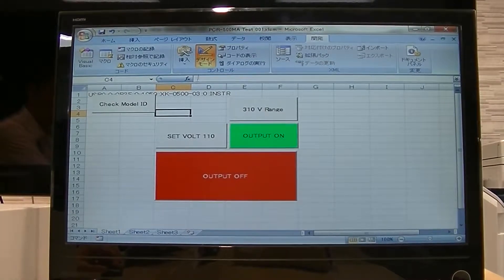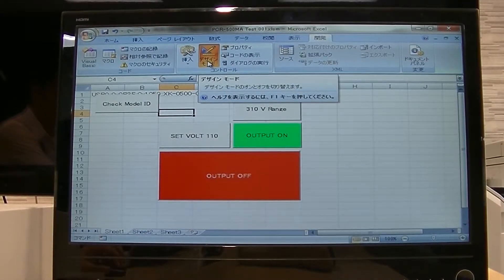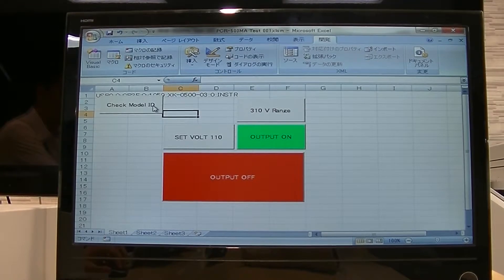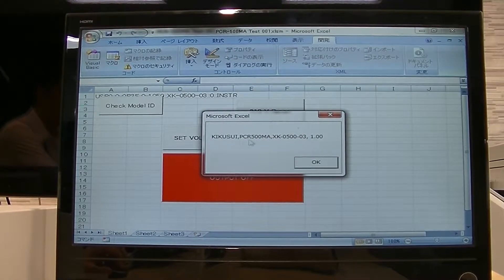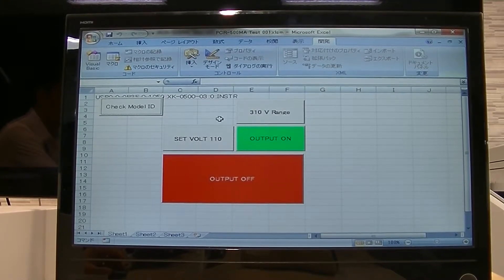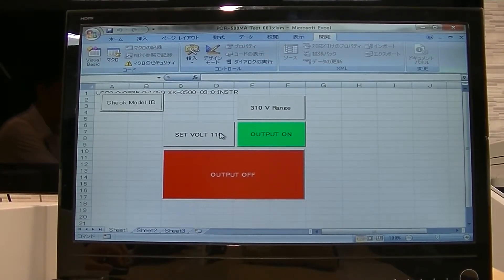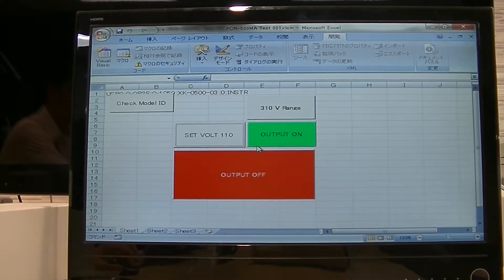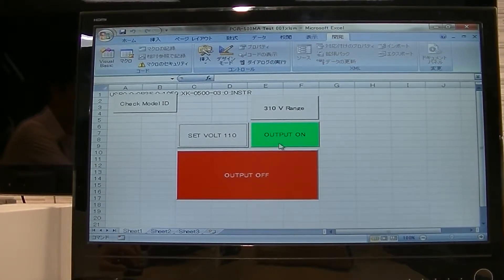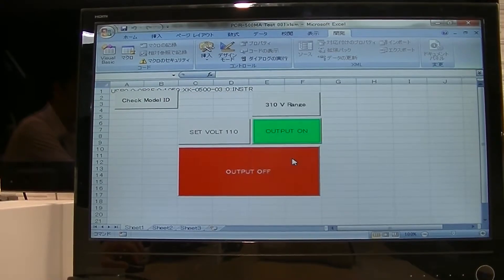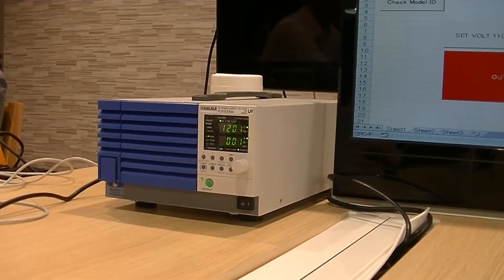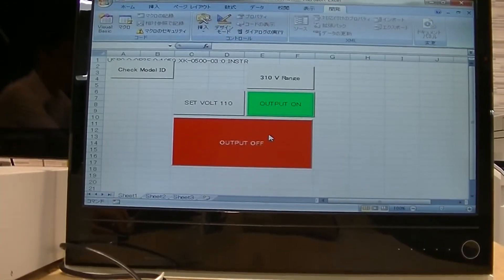Let me test the command that I wrote. For example, Check ID is going to return the ID of the instrument. Then I'm going to use Set to 110 and turn on the output. As you can see, you can use these simple VBA commands to operate an AC power supply or DC power supply.